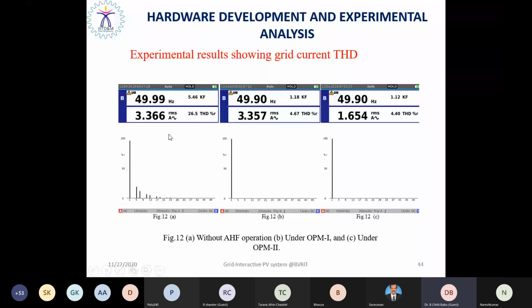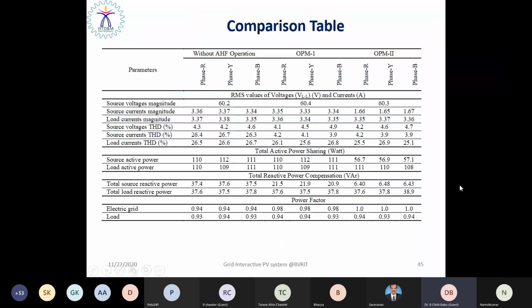Without the controller, the THD of the grid current was 26.5%, and with the help of the active harmonic filter operation and the voltage source inverter or the grid active power converter, the THD has been significantly reduced from 26.5% to 4.67%, as it injects only the fundamental current component. Further, with the multi-purpose or multifunction inverter operation, it has been reduced to 4.40%. This is the comparison table for all three phases without controller, with active harmonic filter operation, or with multifunction inverter operation.